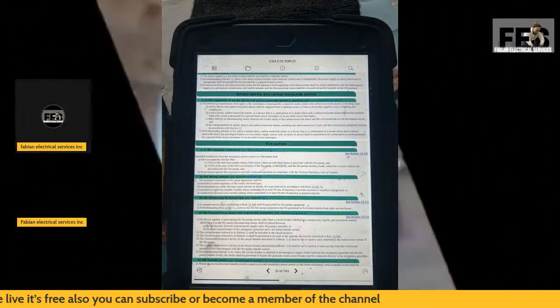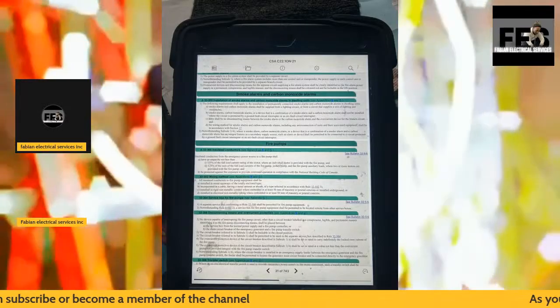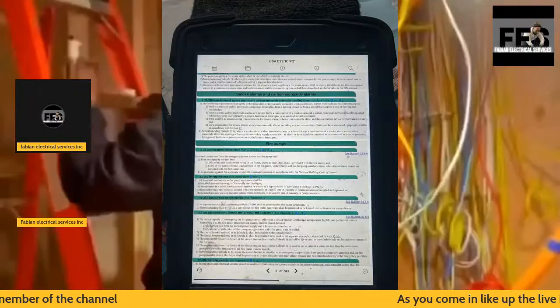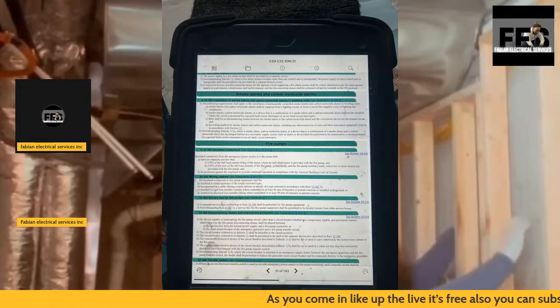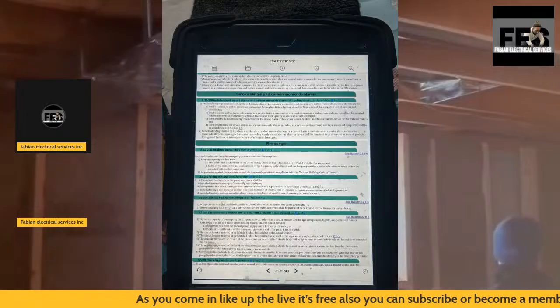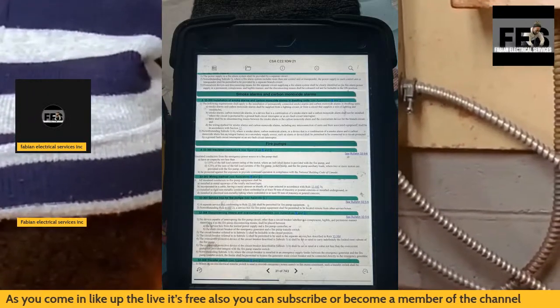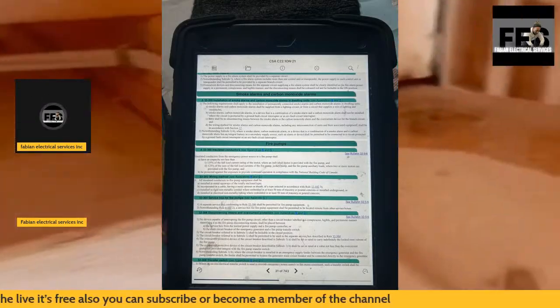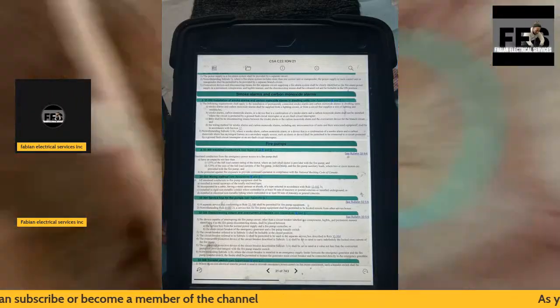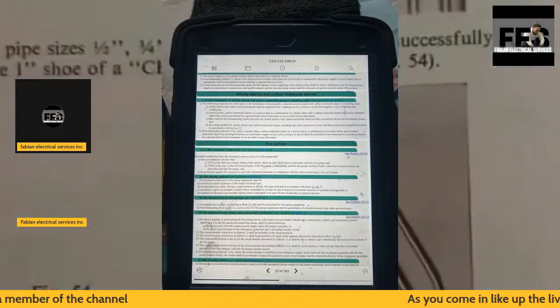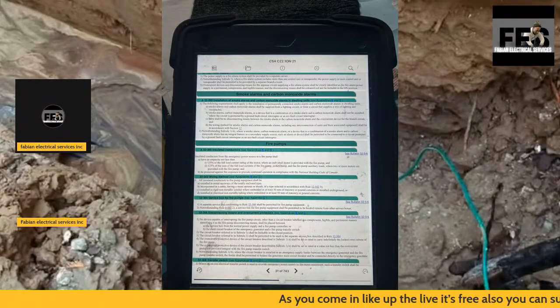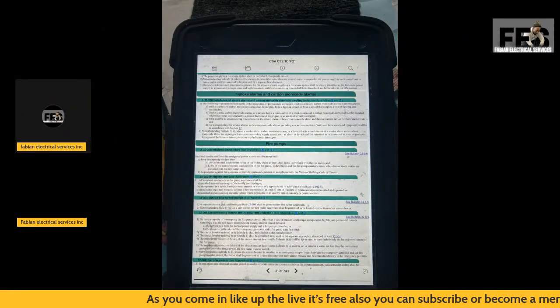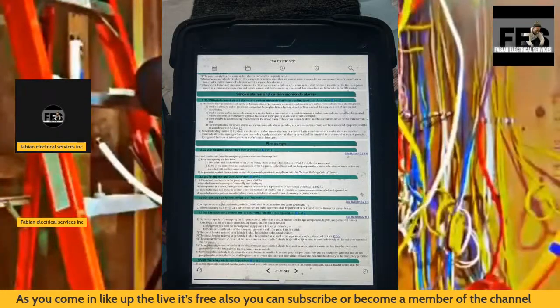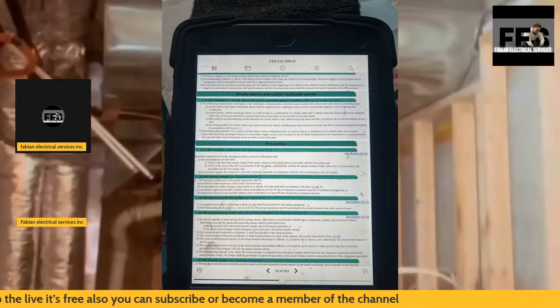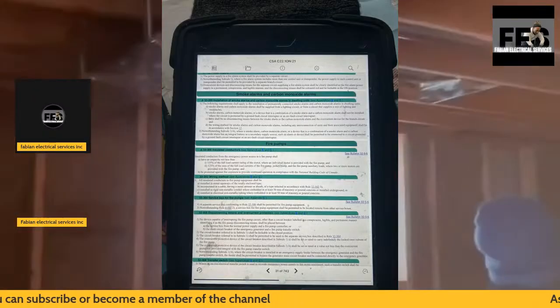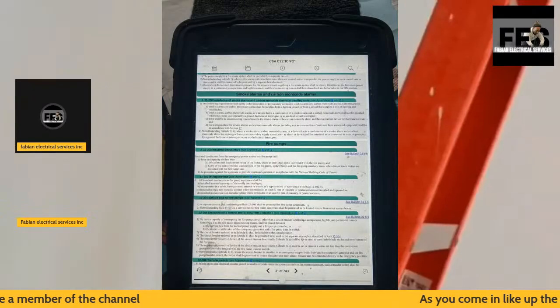For instance, the job site where I'm working, I have to run some wires for the septic tanks, and the distance for the septic tank, depending on which wire size you're using, factors into the voltage drop itself. You just plug the numbers in. It's pretty simple, and you get the cable size you need in order to have the cable and the septic tank work to its full capacity.